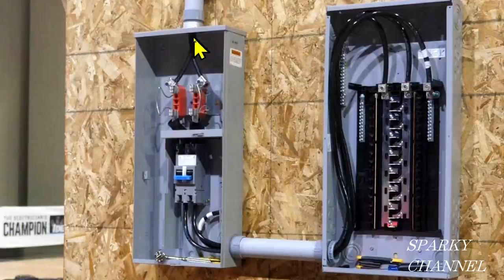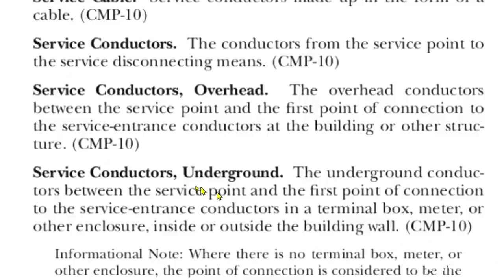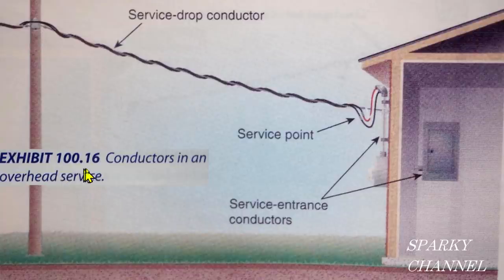Now let's go to the code book and find out exactly what the difference is between these overhead service conductors and these feeder conductors. This is from Article 100 of the 2020 NEC. It says: "Service conductors — the conductors from the service point to the service disconnecting means." And then specifically: "Service conductors, overhead — the overhead conductors between the service point and the first point of connection to the service entrance conductors at the building or other structure." Here we have Exhibit 100.16 in the NEC Handbook.